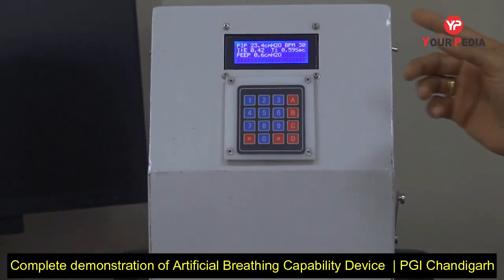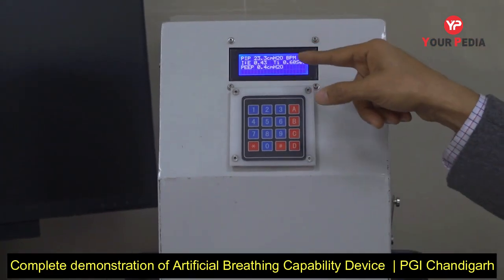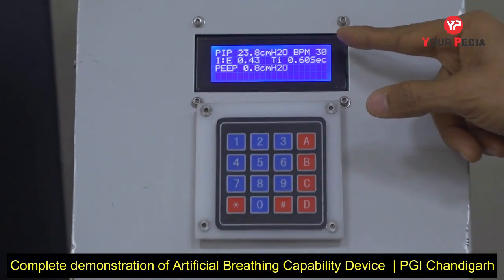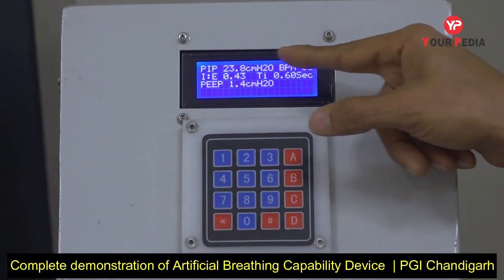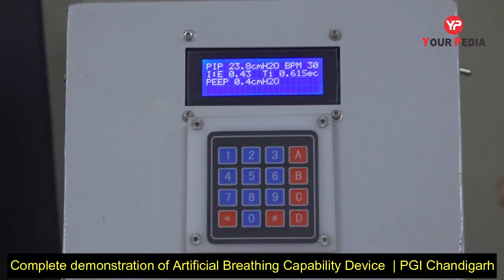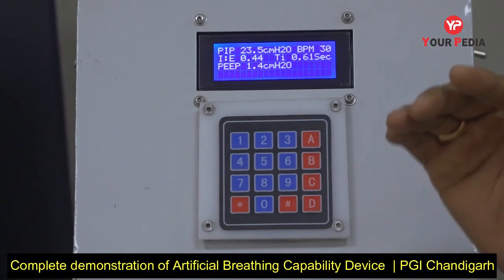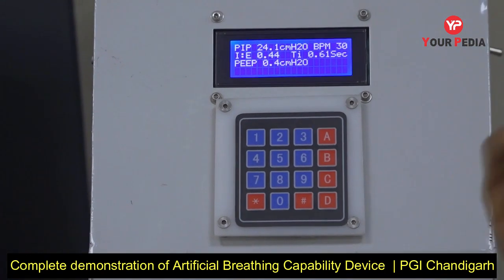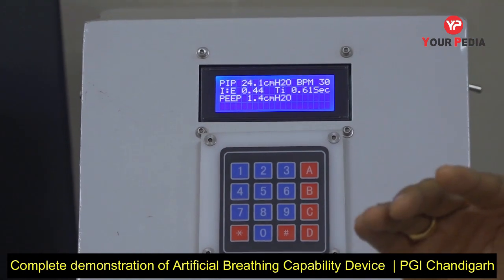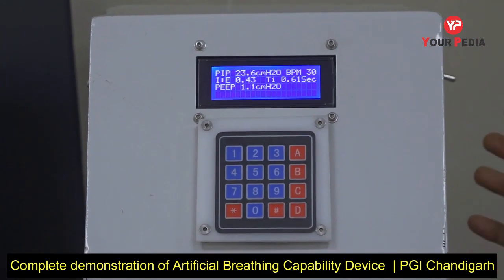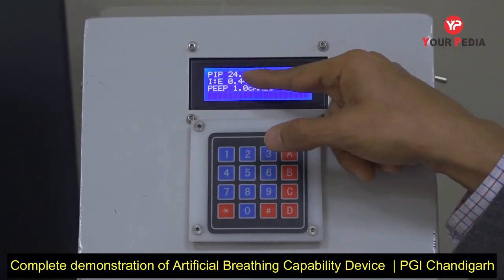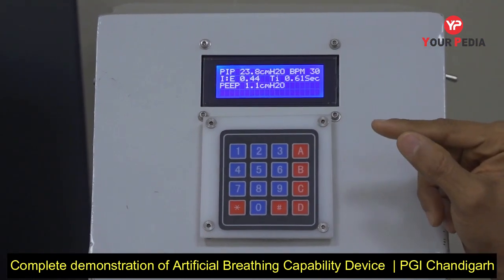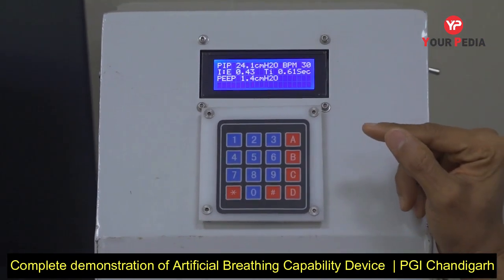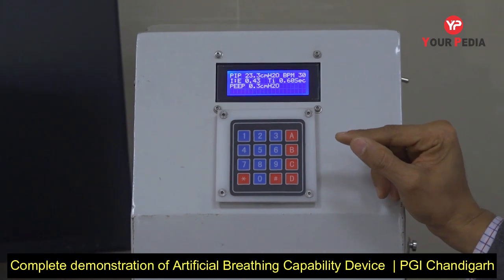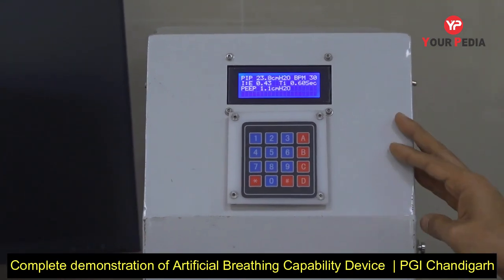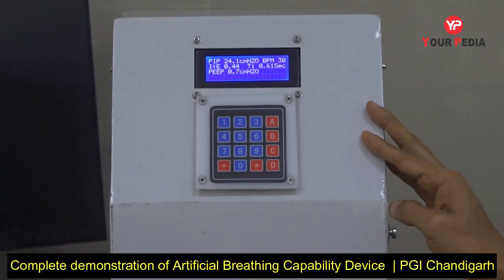In real time, what we can see here is the actual peak inspiratory pressure. You will see we set 24. It is delivering 23.8, 23.6, or 23.5. With each breath, the actual pressure delivered is detected by a pressure sensor located in this device, and these numbers, which vary with each breath, demonstrate the delivered pressure at this time. You can see that the device had no lag time to deliver the set pressure.